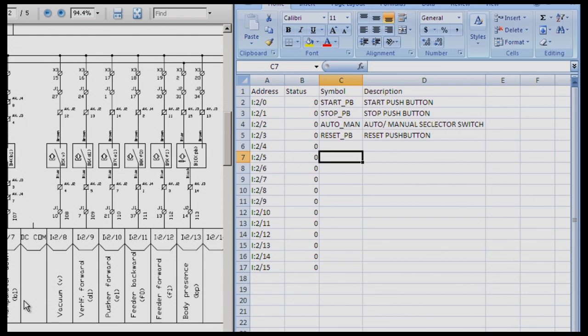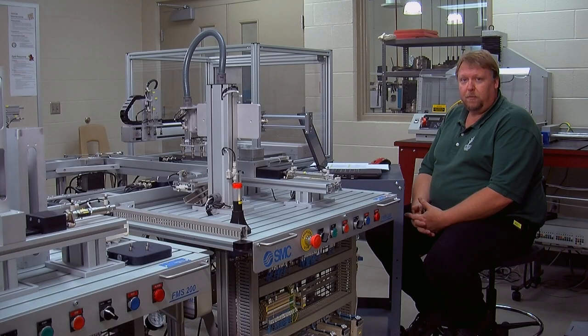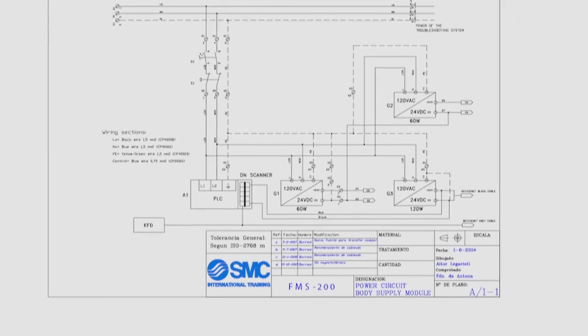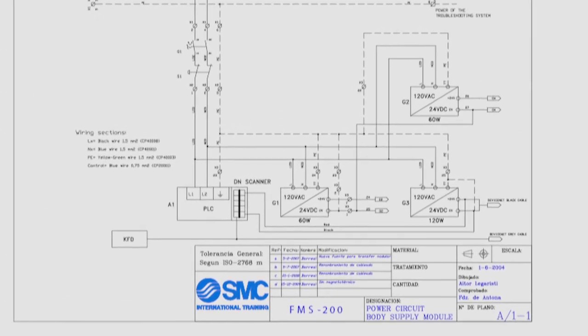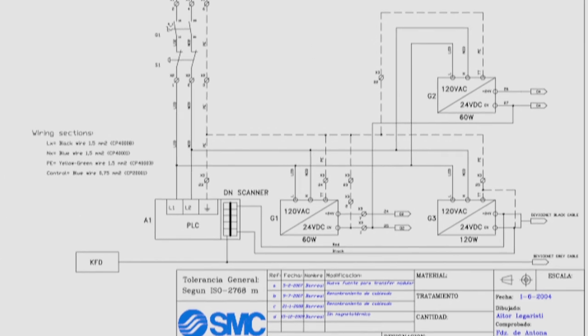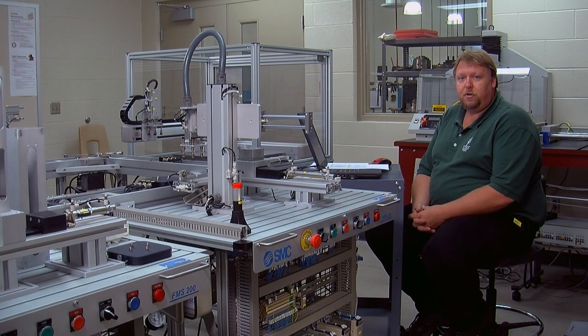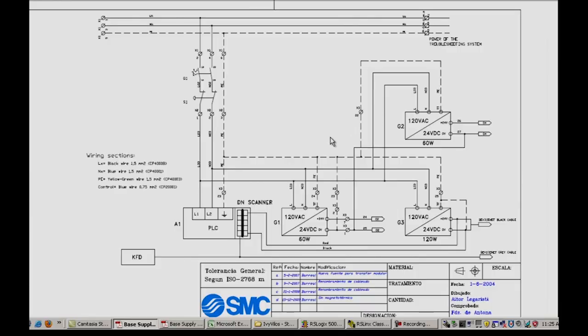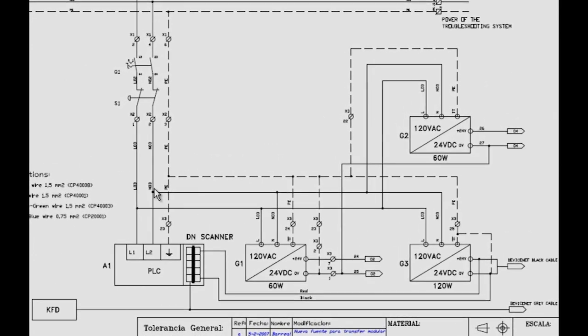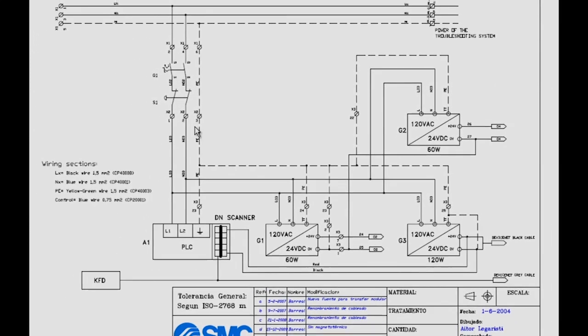With any PLC programming assignment, you must be well prepared. One of the first things you're going to need to have an idea of is your electrical schematics. The designer will have made the schematics for you with all the inputs and outputs on them, but it's going to be up to you to determine how those work. Here is our first page of our schematics — this is mainly the power supply, which doesn't really affect us too much for programming, except to know that the L1 and L2 connections here are being controlled by on-off buttons.